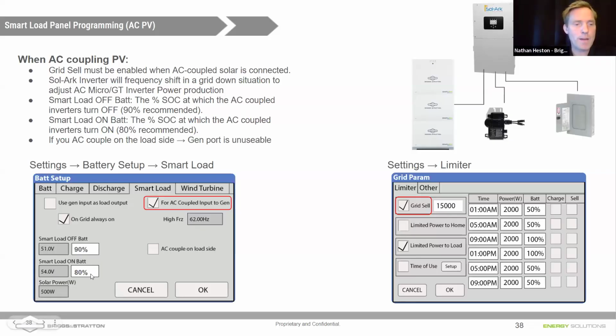If the batteries then drop below 80%, it turns it back on, so those batteries start charging from those microinverters. As Daniel was leading to earlier, we can slow down or speed up the power output coming from the microinverters, or increase or decrease the power output of the microinverter array, by doing what's called frequency shifting. So the Sol-Ark inverter can frequency shift. If you get above 62 hertz on a 1741 SB microinverter, it's going to turn off. So by adjusting that frequency towards 62 hertz, it will reduce the power output of the microinverter.